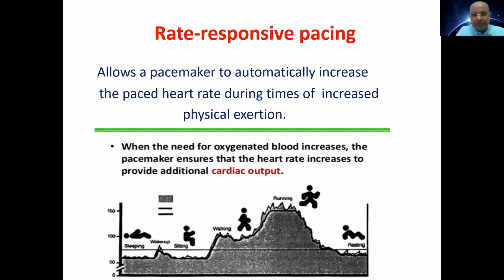Asynchronous mode of pacemaker. We speak about the fourth letter, the R. R is related to rate-responsive pacing. In some pacemakers, sometimes the patient needs the heart rate to be increased due to physiological needs. So they put a sensor for minute ventilation or impedance, or an accelerometer, and this will automatically increase the base heart rate during times of increased physical exertion. If the patient is doing exercise, moving, or under stress, the cardiac output will increase. This is the R letter I mentioned before.